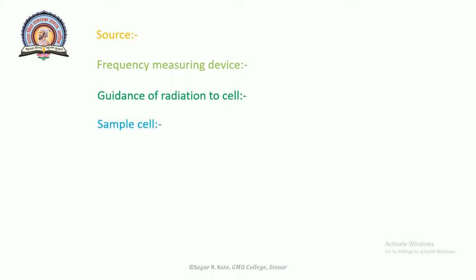Fourth is the sample cell. Different types of cells have been developed depending on the nature of the experiment, each with its own advantages and disadvantages. One of the commonly used cells is the Stark cell, employing Stark modulation technique. The sample cell consists of a long 3 to 4 meter rectangular waveguide. The ends of the cell are sealed with thin mica windows. It is provisioned to evacuate and admit the sample for study. Radiation enters through mica window 1 and what passes through window 2 is detected.